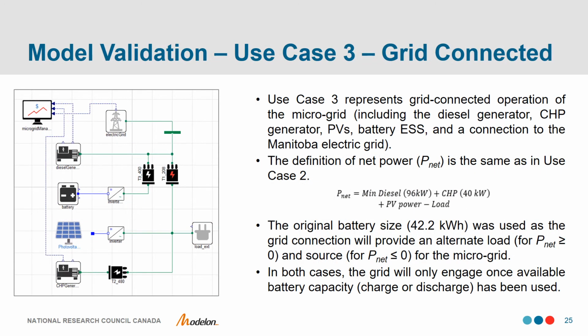Moving on to use case 3, we now introduce grid-connected operation of the microgrid. We'll maintain the original battery size for this study, as the grid connection will now provide an alternate load for the case of surplus power, as well as an alternate source for the case of a shortfall. In both cases, the grid will only engage once available battery capacity has been used.